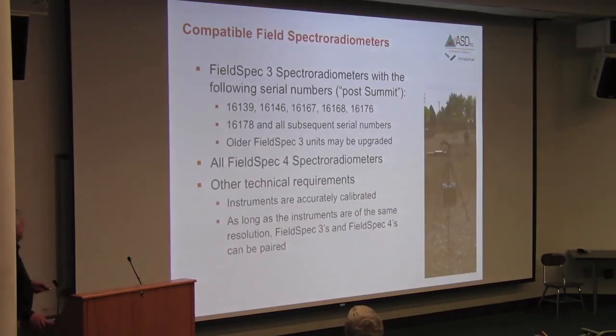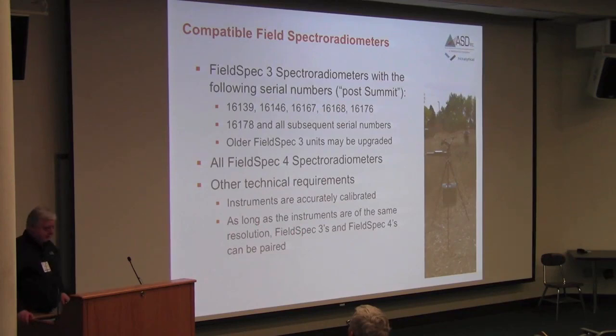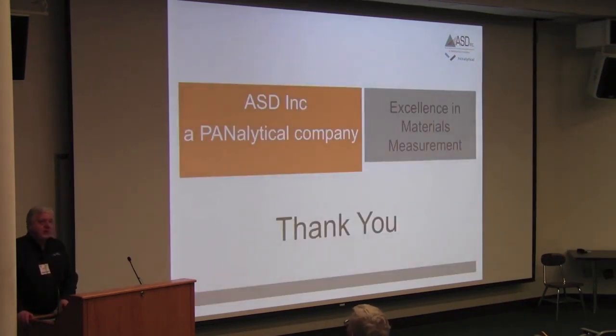Again, I mentioned compatible systems. The FieldSpec 3, that project we called the Summit Project. This was back in 2007 when we changed a lot of the manufacturing approaches. So any instrument with these serial numbers or above is compatible with the software, as are all of the FieldSpec 4s. The key is you want them accurately calibrated, and they need to be at the same resolution. We have a lot of different flavors, and you wouldn't want to mix, say, a standard res instrument and a high res instrument. We have done trials where we mixed FieldSpec 4s, FieldSpec 5s, and FieldSpec 3s, and that works fine as well. So that's it. Any questions?